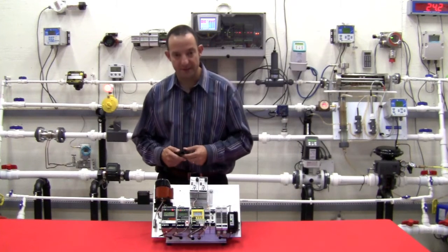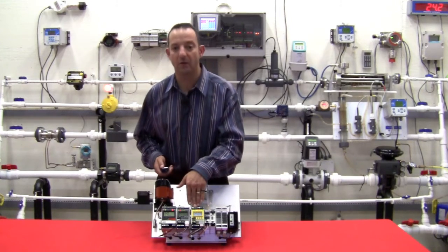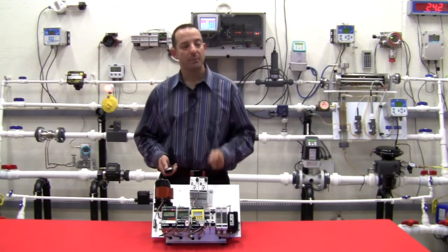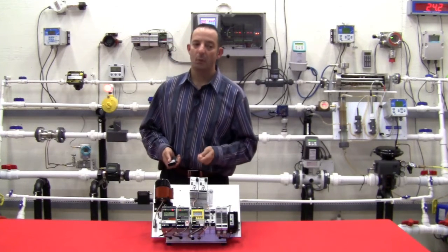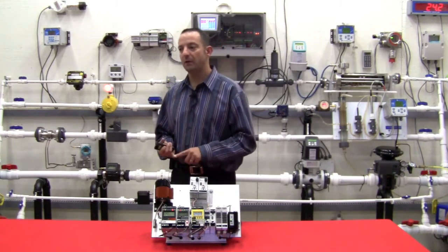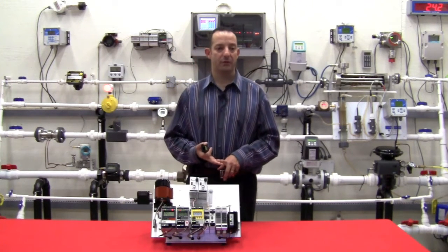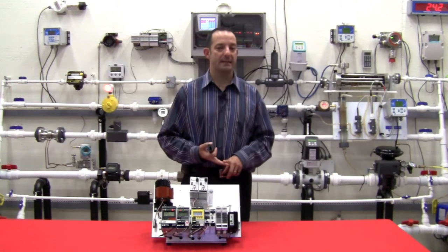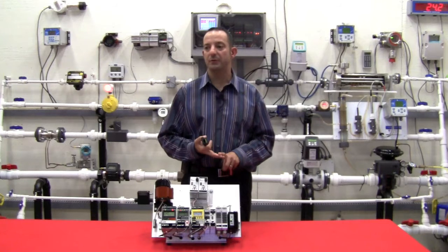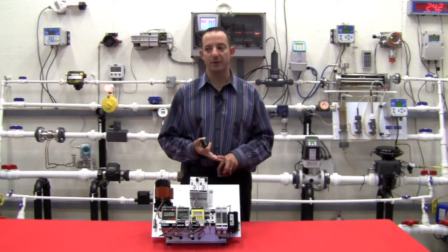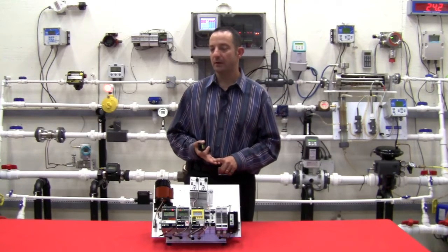So specifically in the demo case, you'll see the SPA2 and the STA alarm trips. These are microprocessor-based units, which means they're extremely stable, and we actually publish 1-year, 3-year, and 5-year drift data on our units. And using that data, customers can lengthen the amount of time between regularly scheduled calibrations of the units, and this is a great time saver for the maintenance department.